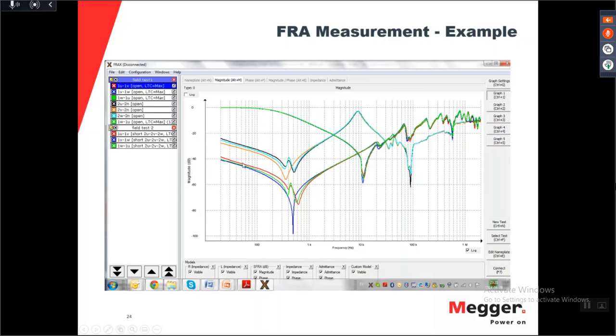You will find a result as a function of frequency. The standard says you should measure from 20 Hertz up to 2 megahertz. It is very clear on how you should measure this. You short circuit the low voltage side, so you actually do the short circuit impedance test again, and then you measure it phase A, phase B, and phase C. When you measure the excitation current, or the open test, as it's called, you have a very large inductance in your transformer. But when you do the short circuit, you actually remove the effect of the inductance. And at the lower frequencies, you see a very large change of the different curves.